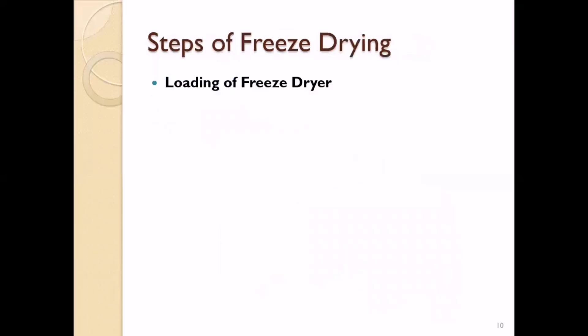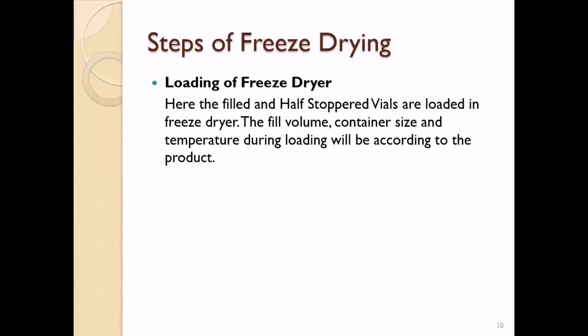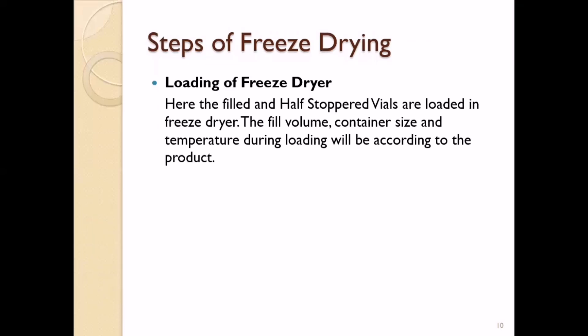The first step of freeze-drying is loading. We have to load the filled containers into the freeze-dryer — specifically filled and half-stoppered vials are loaded. The fill volume, container size, and temperature during loading will vary according to the product, as different products have different container sizes and fill volumes, but the basic loading step remains the same.